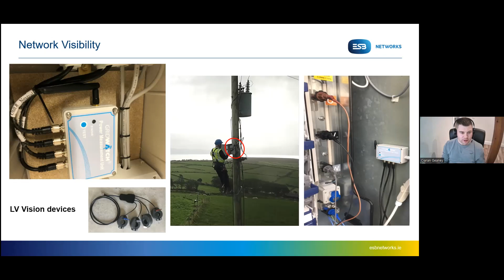I suppose in the network reliability space, at the moment, we have very limited visibility of what's happening on our medium voltage and especially on our low voltage networks. So we've deployed just over 30 transformer monitors where we're able to measure power, voltage and current at different points along the network. That also really enabled us in our customer flexibility trials to assess the impact that these technologies were having on the network. So at a transformer level, we could see when EV chargers would kick in and cars would start charging. We could see the impacts of solar, where there was excess solar in a home being sent out of the home onto the network and up through the transformer. We had minute by minute measurements to be able to assess the impact of all of those things.